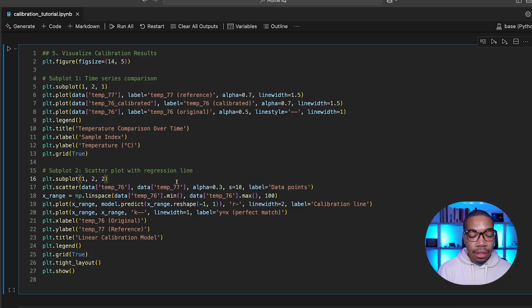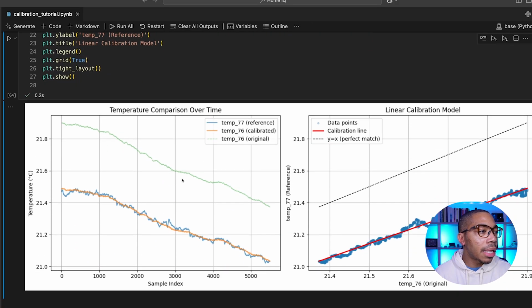Now, to visualize, we're going to create two subplots that allow us to see the temperature versus the sample index and temperature 77, which is our reference temperature, compared to the 76 with our offset line. On this plot, we can see the original temperature 76 here in green, and now we see that the orange and blue traces are completely overlapped as we have now calibrated our temperature 76 probe to our temperature 77, and this is the exact thing we would hope to see.